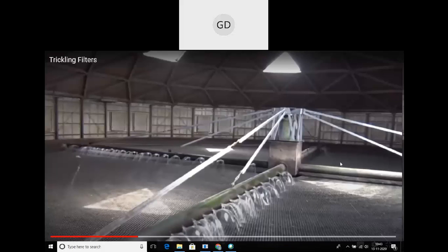Okay, so just now I was telling you about these nozzles, isn't it? You see here this part, the sewage water is coming out. You can see the holes, so those are your nozzles. The water comes out through this central pipe and gets distributed to these rotary arms. These are called rotary arms since they keep on rotating. These are filtering media, you can say. The sewage water trickles over this surface, and below this surface there is coarse aggregate. Now you see again in the video.